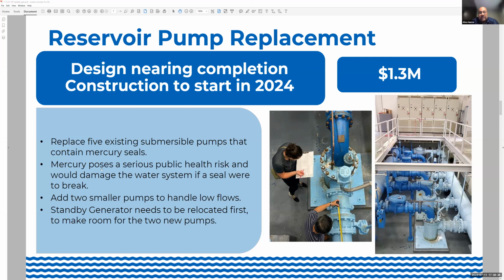What was found is these are all 100 horsepower motors that meet the max day demand of about 2,300 GPM, but during winter months our max day demand drops to about 700 GPM. So these pumps work pretty hard during winter to keep that low flow and become very inefficient, which is why the recommendation is to have jockey pumps in place during low demand.